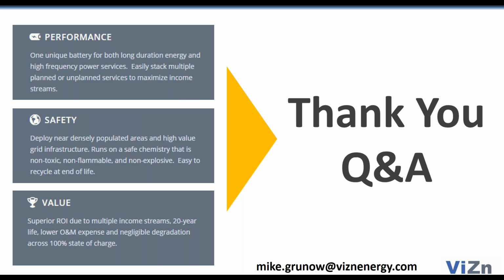I'd be lying if I said there weren't 15 questions in here around cost and price, and I'll respond to these. Bottom line, there's a lot of noise out there in the market in terms of battery manufacturers advertising what their prices are and what their prices are going to be in 5 years, and what their prices could be if you submit a purchase order for, say, 1 million units. The fact of the matter is that depending upon the battery technology, if it's lithium ion, it makes up between 20 and 30% of the overall turnkey system cost, the first cost. But if you look at flow batteries, it ranges from 40 to 75% of the overall turnkey system cost. It's also critical to take into account operations and maintenance expense for things like massive change-outs of lithium-ion cells, which could definitely have to happen between years 7 and 15 in a project, and other operational expenses such as auxiliary loads and large HVAC loads that come up in various climates.